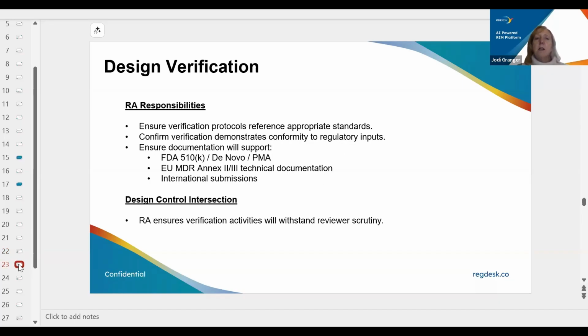For design verification, your verification protocols should be reviewed by regulatory. The reason is that most of the time, the output from those verification activities is going to feed into regulatory submissions. So you want to ensure that you've got regulatory review and input in the beginning and not after all of those reports are completed. So the verification needs to have a pathway to demonstrate conformity to all of the regulatory inputs that were generated during the design input phase. It has to ensure that the documentation will support your various submissions globally. So that's the intent of having regulatory in the loop during this verification process.